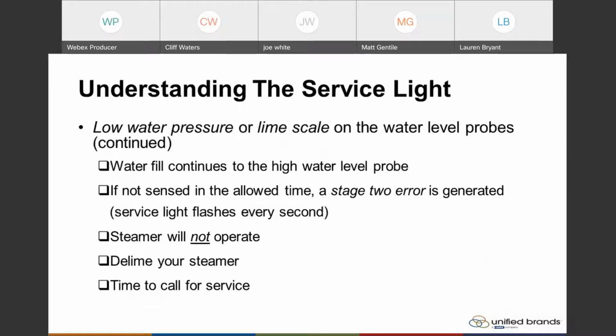Why does that happen? I'm certain Jim is asking that question. Well, Jim, that's because the water starts to fill. The low probe will be the first one that it would find because it's filling from the bottom up. And if it didn't see that probe, it's going to go back and look for that high water level probe because the unit will operate on 1 probe. So water fill continues to the high probe. If not sensed in the allowed time, a stage 2 error is generated.